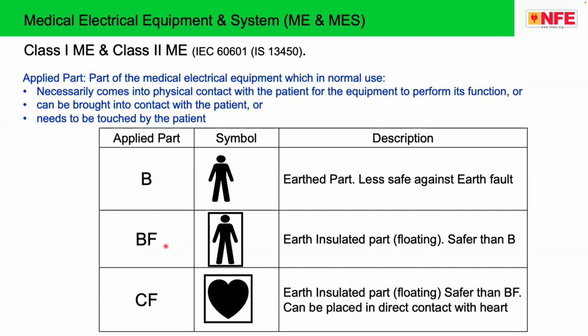Type BF, insulated part, floating, safer than B. In this particular case, the blood pressure cuff, the ultrasound transducers, the probe, infant incubators, the component and the temperature probe that controls the infant, a pulse oximeter, the sensor attached to the finger, all these are classified as BF. CF is much more safe.